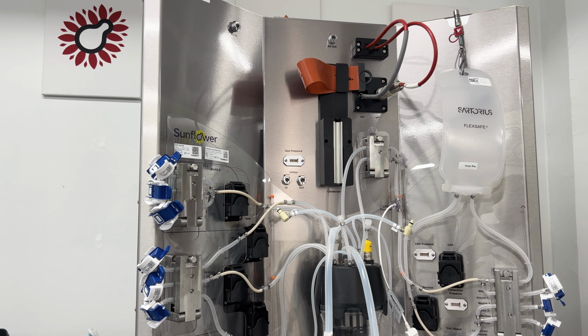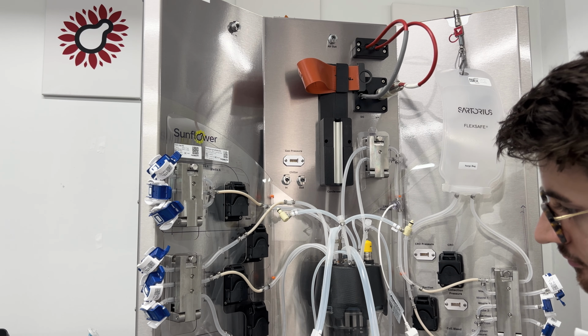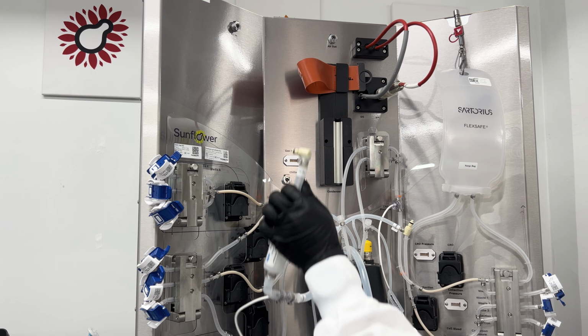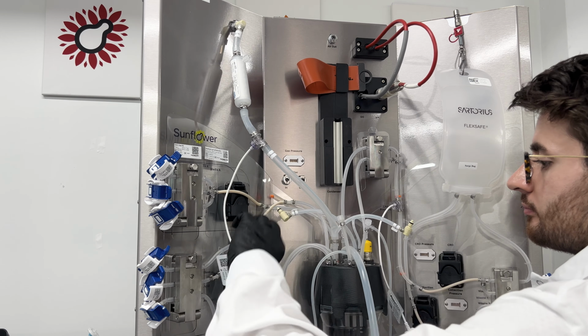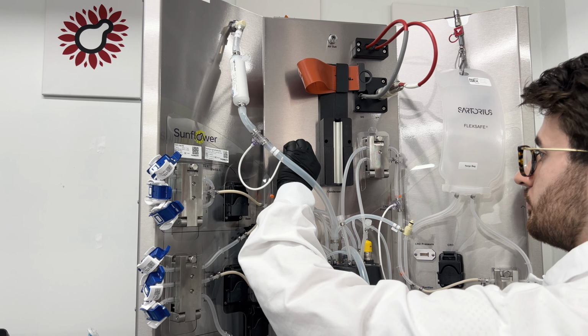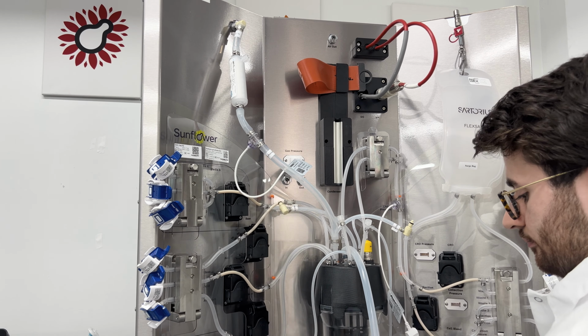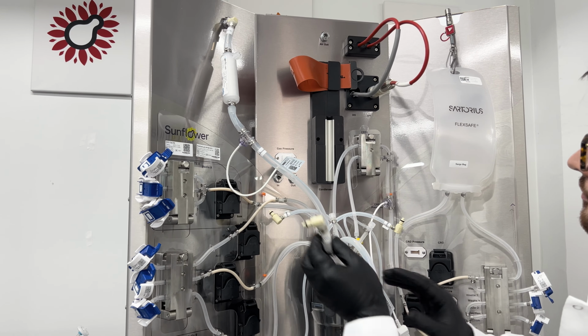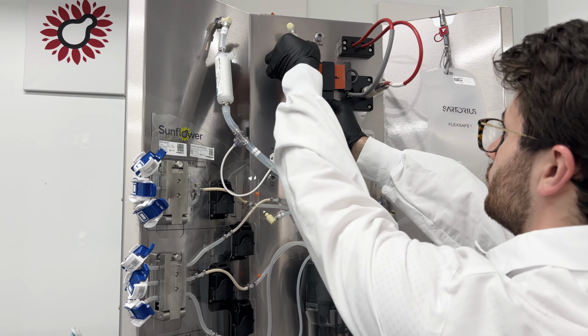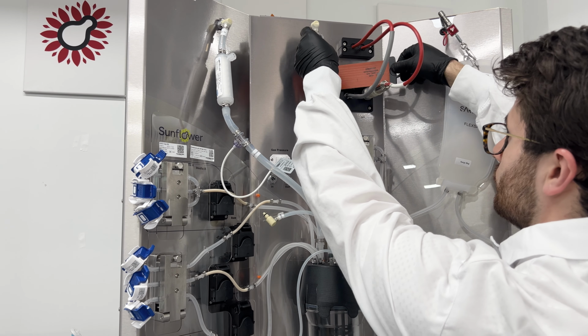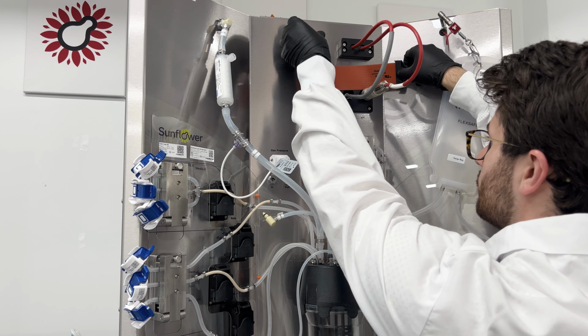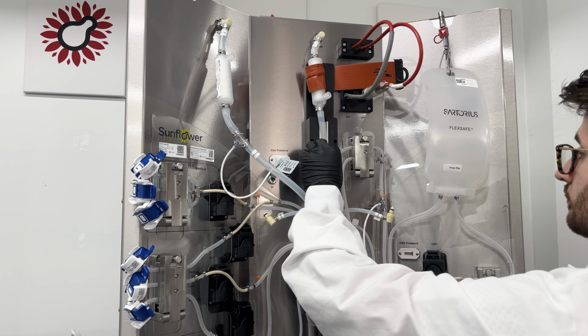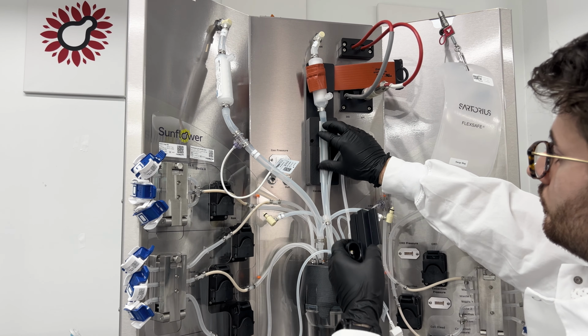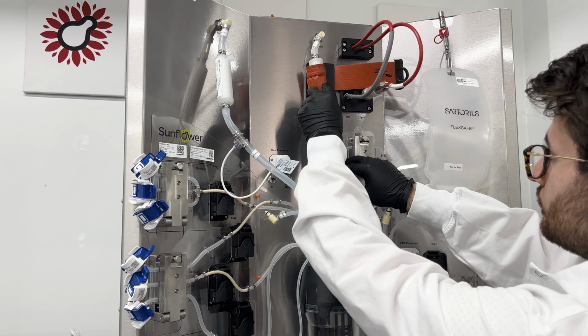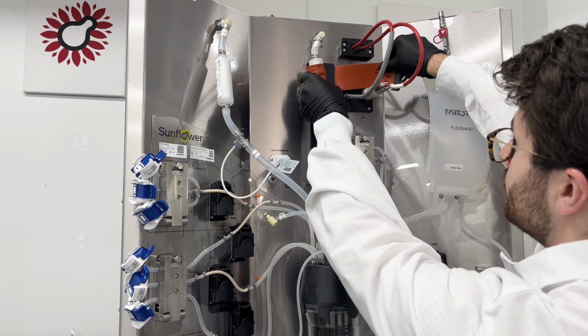The air and oxygen that the bioreactor requires during operation are supplied through the air-in line, which we will connect to the system at the top of the left panel. The gas pressure sensor plugs into the center panel here. Gases vent through the air-out line, which threads through the filter heater. We'll tighten the filter heater around the filter, then plug in the quick disconnect. After we seat the tubing below the filter in the condenser channel, we can place the magnetic condenser cover back over the condenser.